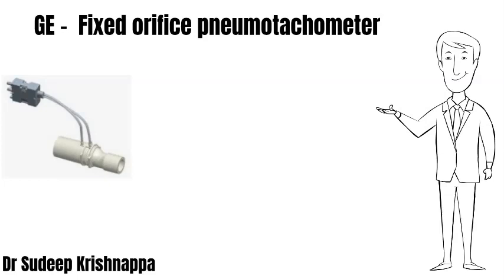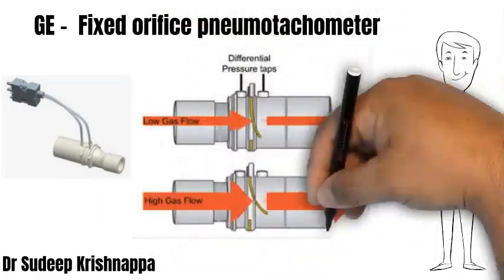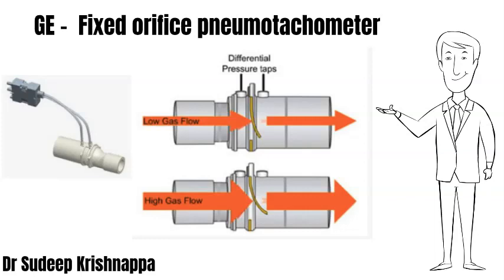The picture on the far side of the slide shows the actual pneumotachometer. The white tube-like structure houses the orifice across which the pressure drop happens. The two tubes leading away from the system help in measuring the pressure on either side of the orifice, thereby measuring the pressure drop and the flow. The second picture shows a cross-section through the pneumotachometer device, showing an orifice in orange and the direction of gas flow.